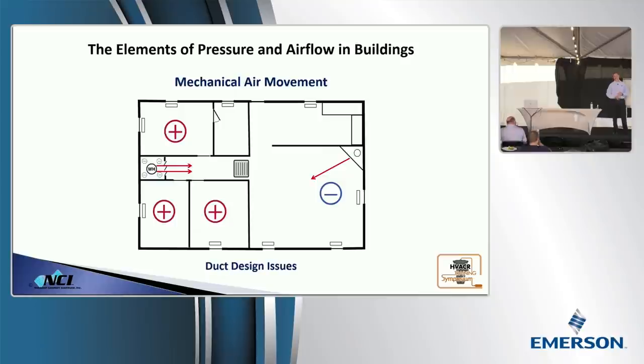Now, what's interesting, I mentioned the 2015 fuel gas code earlier. If you look at the definition of a draft hood and the definition of a relief opening, they're the exact same. Try looking it up, see what the definition is. You'll go, oh, I didn't know that's what it was. So as we look at this, as pressure changes, air starts to flow one direction or the other. And it can either go up a flue or it can go down a flue.